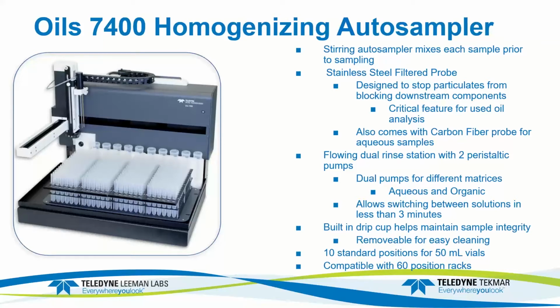And there's some video, we'll show you that in a second. It also has a stainless steel probe, which just a little image popped up in the middle there, that prevents crud, for lack of a better term, that may be in the oil from plugging up the auto sampler. This is a really nice feature, the way this operates. So generally anything that can fit through those little holes will fit through the pump tubing and fit through the nebulizer, and we'll talk about that. It also is available with a carbon fiber probe, so you can do aqueous samples, and that would be for people who want to do coolants.